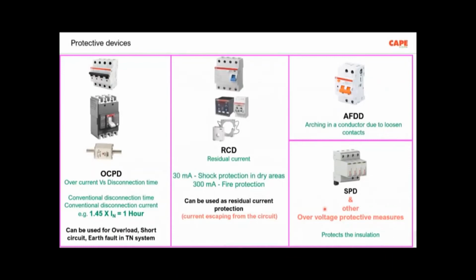Say, for example, as I said in the previous slide, a fault on the high voltage side of the transformer can create a failure and shock hazard inside our house. So the overvoltage maximum allowed inside our building is 1200 volt for 5 seconds. More than that is not allowed, and we need to actually implement all these protective measures in our building. So I would recommend that the electrical designers, those who are listening to the program, please start looking seriously into this particular subject.